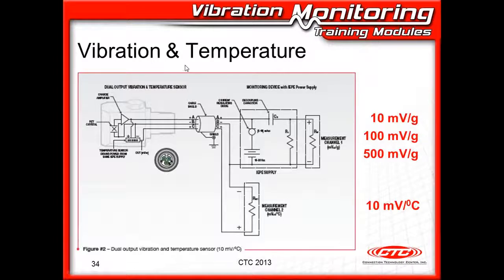Vibration and temperature sensors, a dual output sensor. We use the IEPE power supply inside your data collector to power this sensor. So this will power the sensor. It will also measure the vibration. So typical of any accelerometer, we're powering it, and we're measuring the vibration.